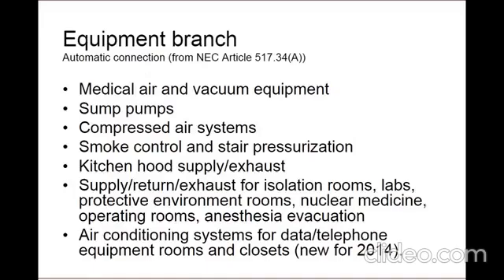The equipment branch is the third branch, but this one is actually listed in two sections of the NEC. It's in Article 517.34, both Parts A and Parts B. Part A requires automatic connection, and Part B lists items that are permitted to actually be manually connected. So the following items are required to be automatically connected to the equipment branch: medical air and vacuum equipment, sump pumps, including their controls, compressed air systems serving medical and surgical functions, smoke control and stair pressurization systems, kitchen hood supply and exhaust systems, supply return exhaust systems for isolation rooms, labs, protective environment rooms, nuclear medicine areas or other areas where radioactive material is used, operating rooms, and anesthetizing evacuation equipment.